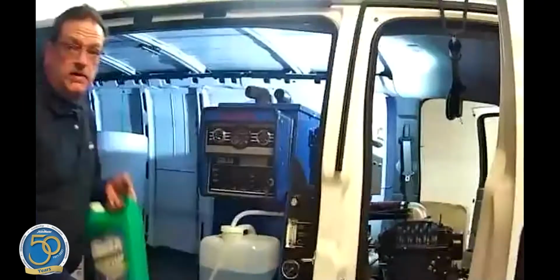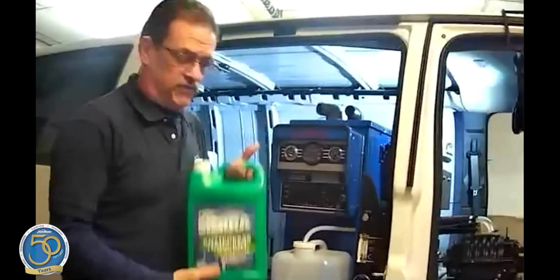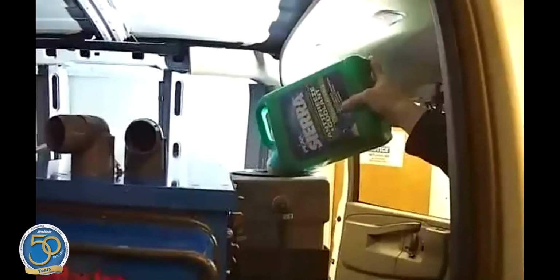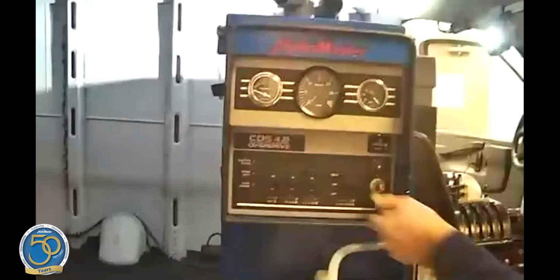Now what you're going to do is drain the water box down halfway and add 1 to 1.5 gallons of concentrated antifreeze, pouring it into the round lid on top of the water box. This is to freeze guard your heat exchangers, pump, and regulator. After draining it, pour the concentrated gallon of antifreeze into the water box.